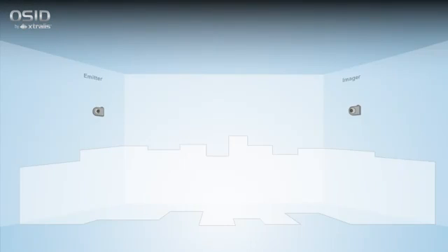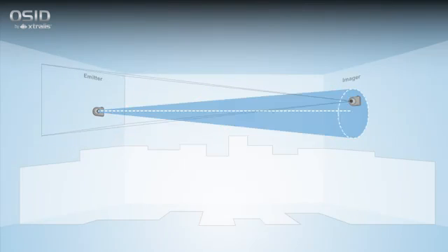OSID installation and commissioning is simple because exact alignment between the imager and emitter is not required. An imager can locate and lock in an emitter that is only roughly aligned, thanks to the imager's wide field of view. Because OSID uses a wide-angle imaging sensor, its software can compensate for vibrations and building movement. With this unique feature, OSID is able to track the signal from an emitter fixed to a wall that flexes up to four degrees in any direction without generating a fault or false alarm.